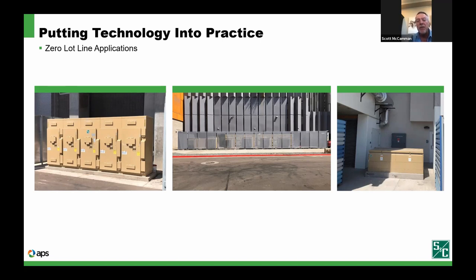On the far right is an example of the Vista switchgear, like Henry was explaining. This is a six-way switchgear, so it gives us the extra two bays compared to the typical pad-mounted equipment with four compartments, and again, space at a premium. This is also adjacent to an alleyway, and it does have a gate that's open right now. What you're seeing is actually the termination side, which is crucial for the crews to have their clearances to be able to work on those terminations.